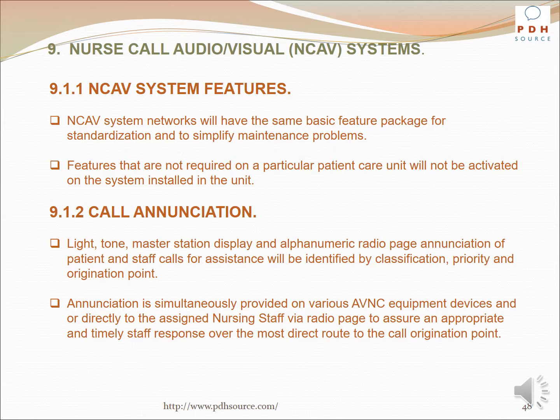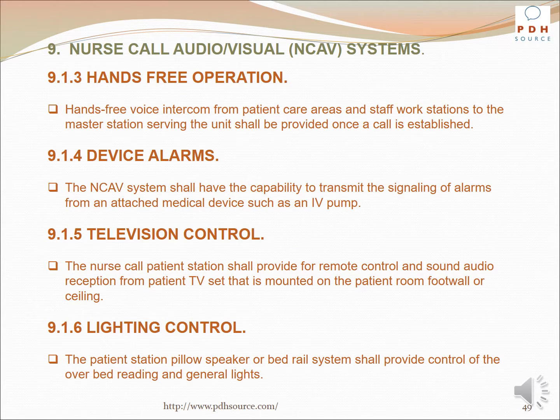Annunciation is simultaneously provided on various AVNC equipment devices and/or directly to the assigned nursing staff via radio page to assure an appropriate and timely staff response over the most direct route to the call origination point. Hands-free intercom from patient care areas and staff workstations to the master station serving the unit shall be provided once a call is established.